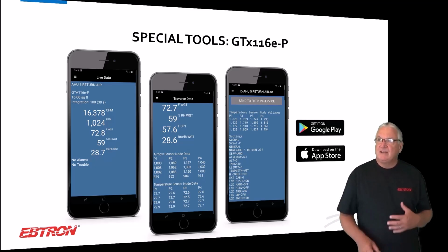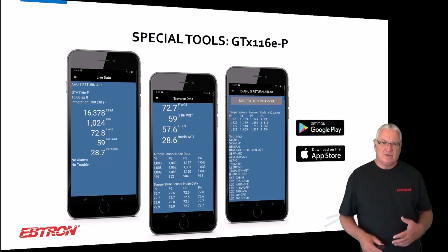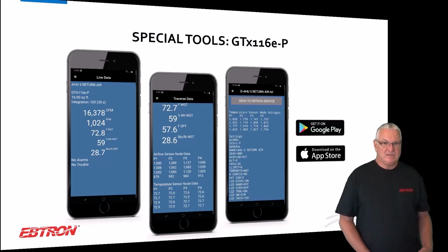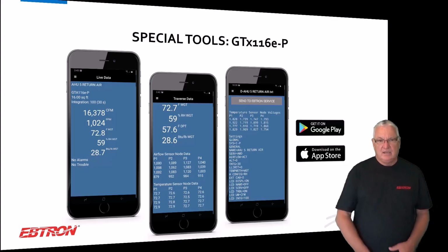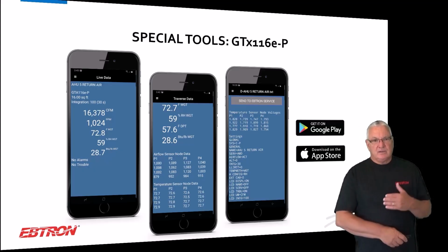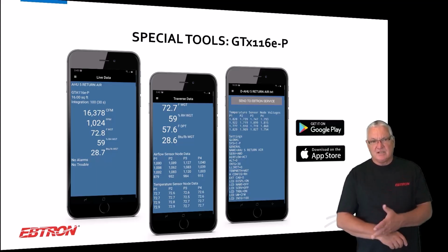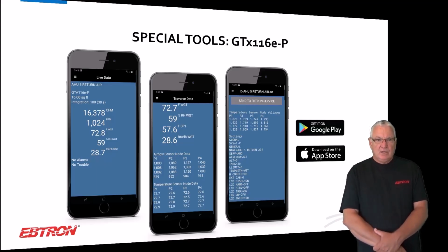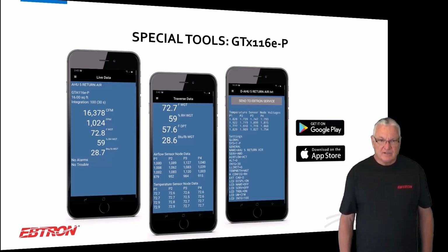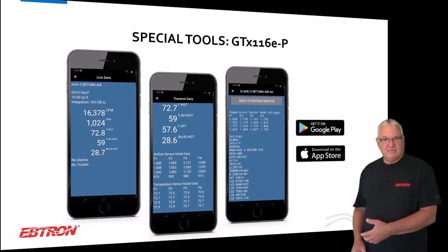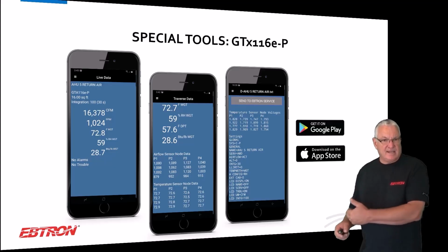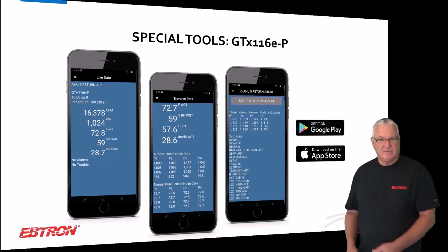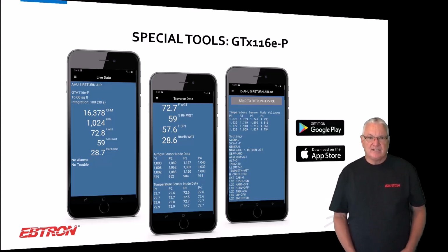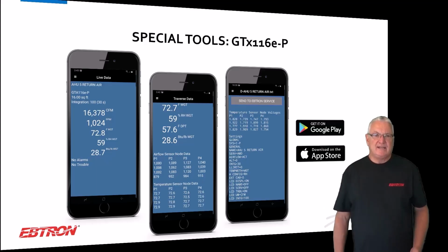which means we integrate the information in the transmitter so that, like in this case here, it says integration 100. EBTRON samples every 300 milliseconds, calculates flow every 300 milliseconds on a 1 to 16 sensor unit, okay? So an integration buffer of 100 means it takes 30 seconds to do an integration of 100. You don't want to sit there for 30 seconds. So we have an integration buffer in the transmitter that's always keeping the last 100 data points, in this case. So that when you shoot this thing at the transmitter and get back the results, it's instantaneous, you're not waiting.